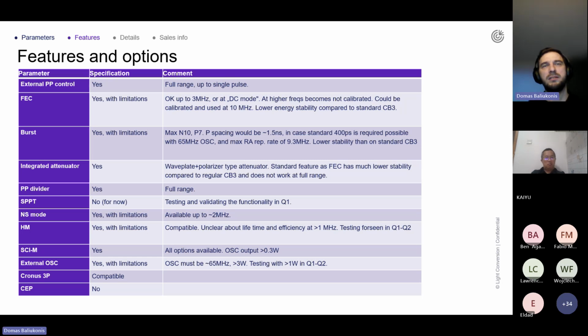But to overcome this issue, we added the optical attenuator, which we use as the attenuator instead of fast energy control, because the fast energy control attenuator is basically standard for all the Carbide CB3s. So in this case, we make it the other way around. We make the optical attenuator a standard, and fast energy control an additional option. It will always be equipped in the laser, but it will be disabled by default.